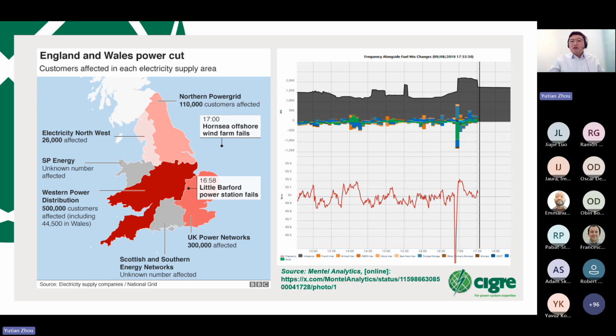unnecessarily. And around a minute after the fault, one of the gas turbines, again at the Little Barford power station, which is about 210 megawatts in total, was shut down for safety reasons. This is due to too much steam pressure building in its pipework. So this then led to the total loss of generation coming up to just shy of 2 gigawatts.